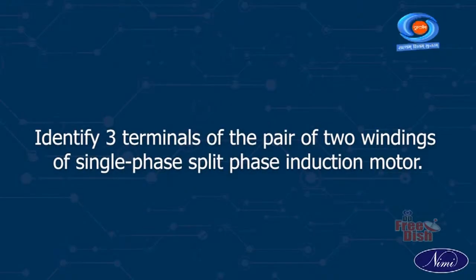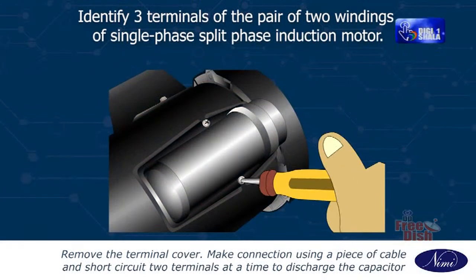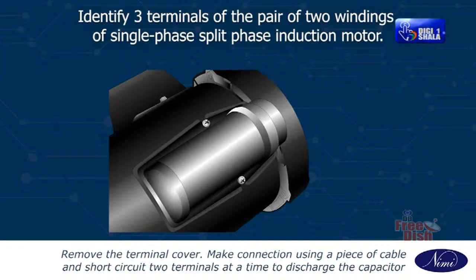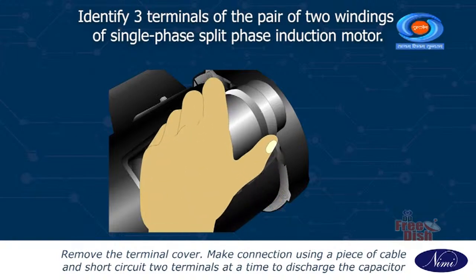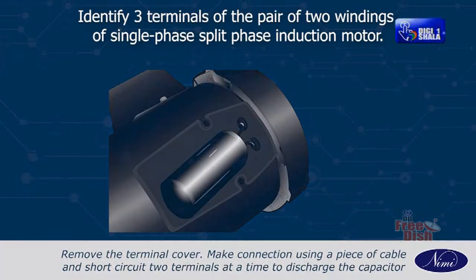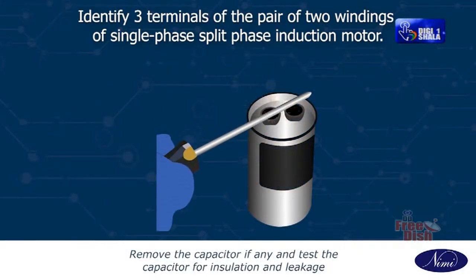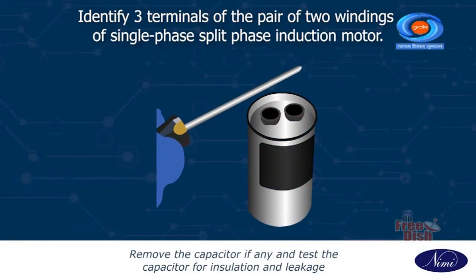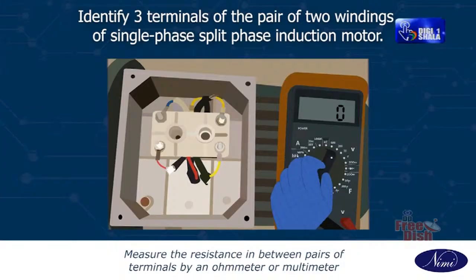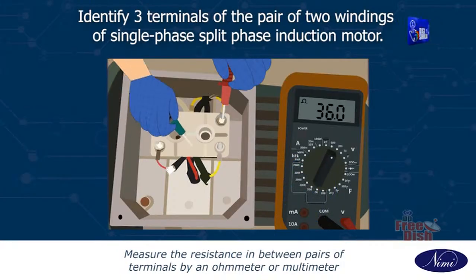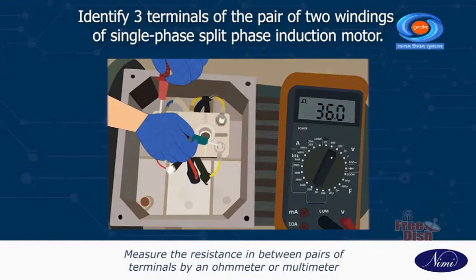Identify 3 terminals of the pair of 2 windings of single phase split phase induction motor. Remove the terminal cover. Make connection using a piece of cable and short circuit 2 terminals at a time to discharge the capacitor. Remove the capacitor if any and test the capacitor for insulation and leakage. Measure the resistance in between pairs of terminals by an ohm meter or multimeter.